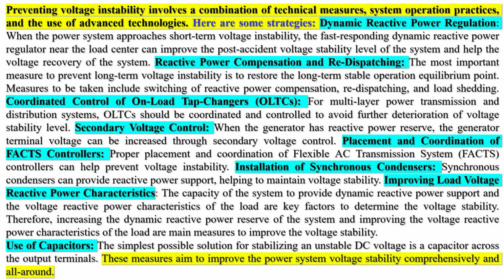Improving load voltage reactive power characteristics. The capacity of the system to provide dynamic reactive power support and the voltage reactive power characteristics of the load are key factors to determine the voltage stability. Therefore, increasing the dynamic reactive power reserve of the system and improving the voltage reactive power characteristics of the load are main measures to improve the voltage stability. Use of capacitors. The simplest possible solution for stabilizing an unstable DC voltage is a capacitor across the output terminals. These measures aim to improve the power system voltage stability comprehensively and all around.